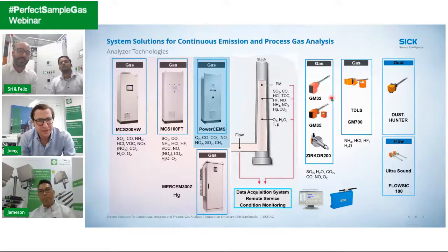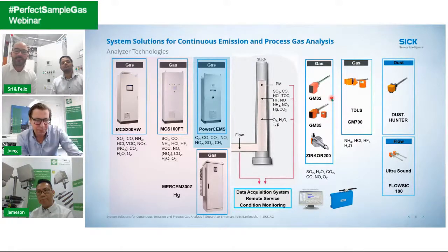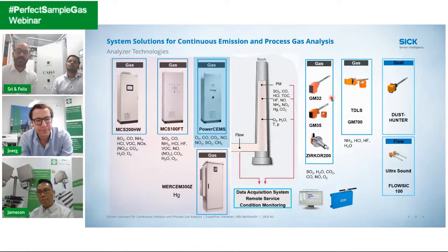Here we are using gas coolers to cool down the sample gas coming from the heated sample line. By doing so, we extract the water from the process gas, which allows us to measure the gas composition in dry gas, a little easier than using hot, wet gas. The benefit here is that the system is not as highly sophisticated as the hot wet measurement technology. However, in this case you are unable to measure water and water-soluble components, since they are usually extracted by the sample gas cooler.